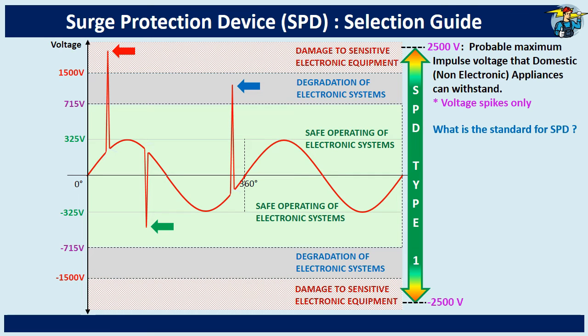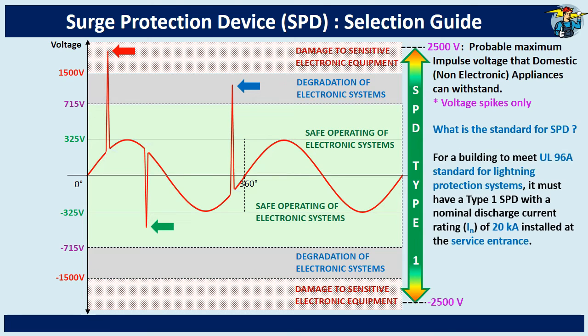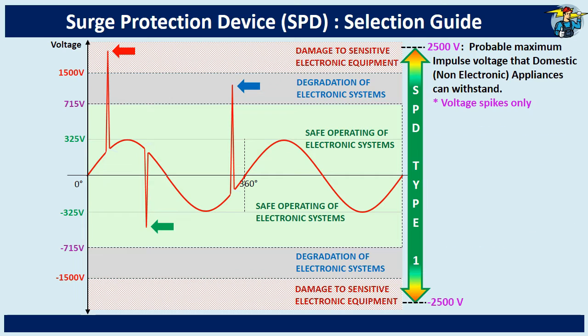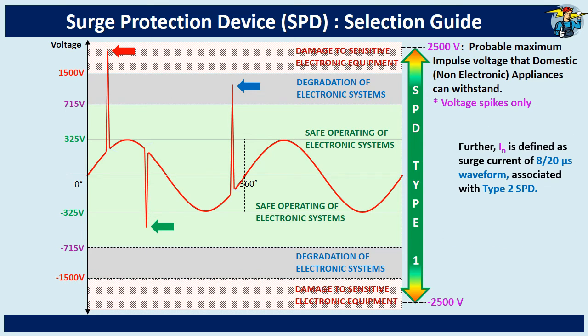What is the standard for an SPD? For a building to meet UL96A standard for lightning protection systems, it must have a type 1 SPD with a nominal discharge current rating of 20 kA installed at the service entrance. Further, IN is defined as surge current at a 8/20 microsecond waveform, associated with type 2 SPD.